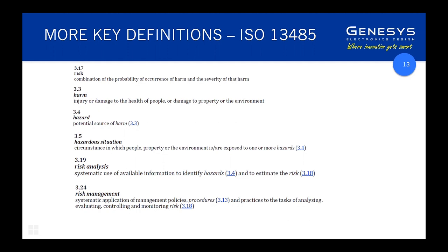So it brings us to risk analysis. It's the process, and this gets back to the systematic process I mentioned at the start, of systematically identifying hazards and working through to say what is the probability of the hazardous situation occurring and what is the probability of consequential harm, and the combination of those two elements gives rise to an assessment of the level of risk associated with that particular sequence of events.